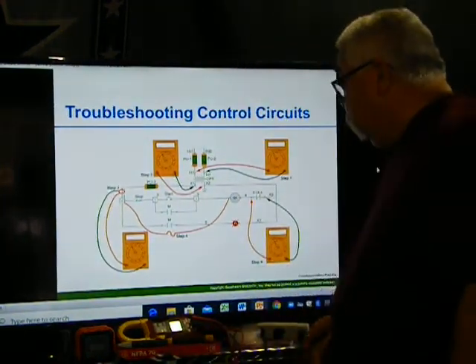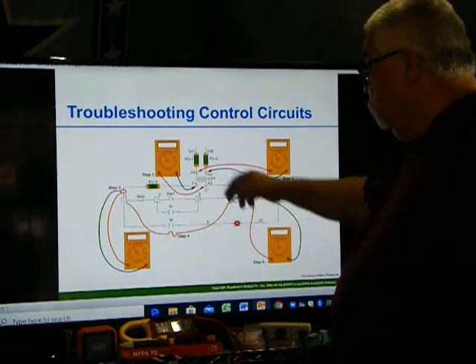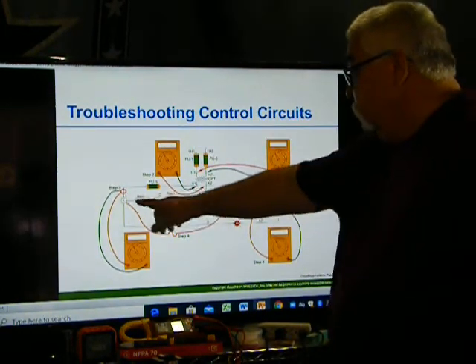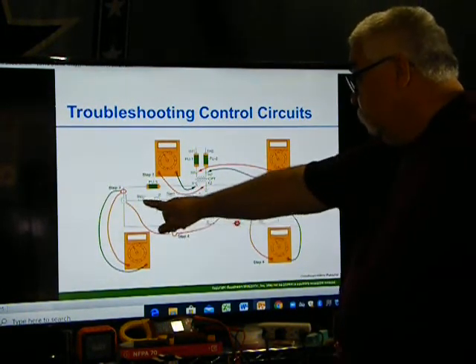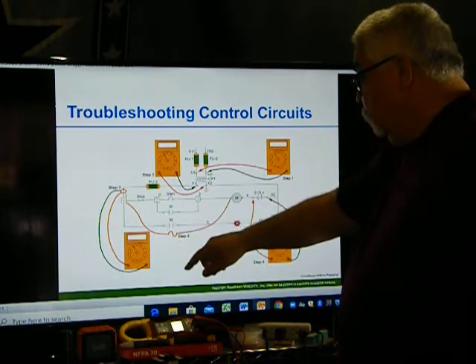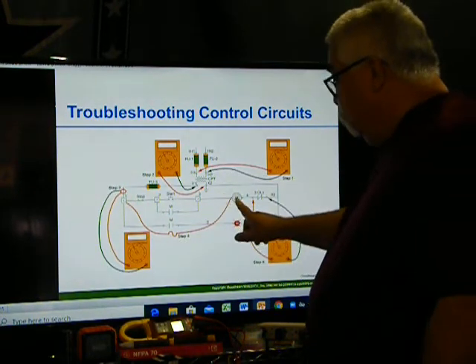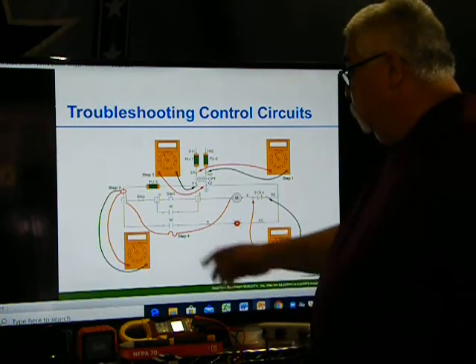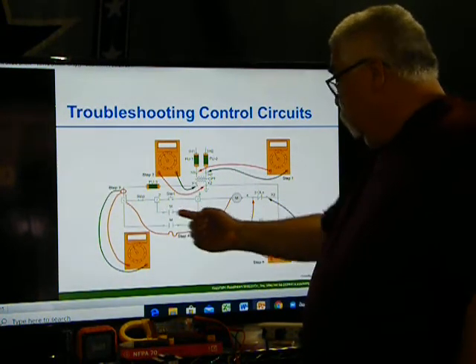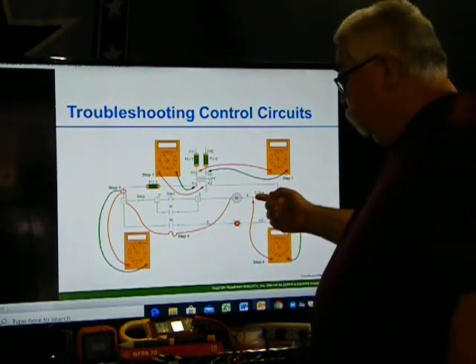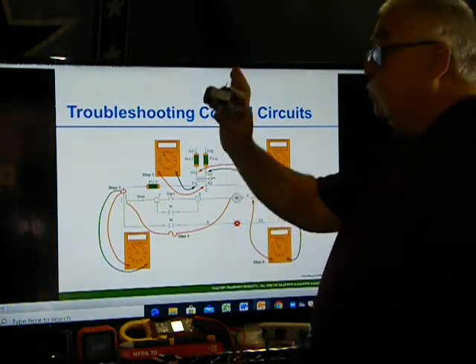Alright, so control circuit. This is a control circuit. We got power coming to the transformer. Transformer goes in, stops, starts. Here's a stop, here's a start. Here's my relays, and here's my contactor. Okay, so this is my normally open. Here's my normally closed. This is where the overloads are at. So this part here is always closed. This is my overloads. That's this part right here.